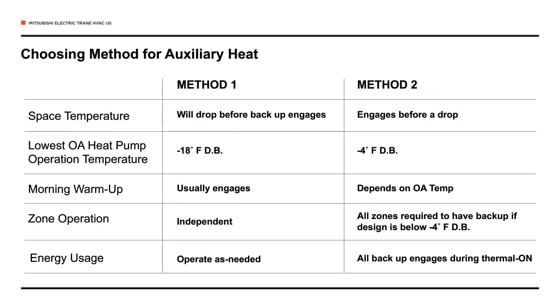Just a little bit of a summary. I'm not going to go through each of these. Method 1, the space-by-space method: space temperature has to drop. By definition, you have to deviate from set point for that to engage. So if you have that deviation set at, say, 9 degrees below set point, you might get some comfort complaints at that point. So you want to give some thought to where you set that, as far as when that auxiliary heat kicks in. With method 2, or the global method, we're switching based on ambient temperature.